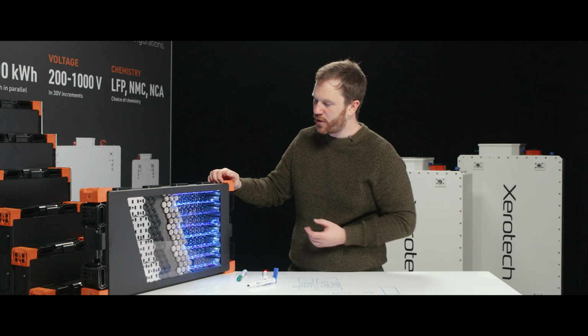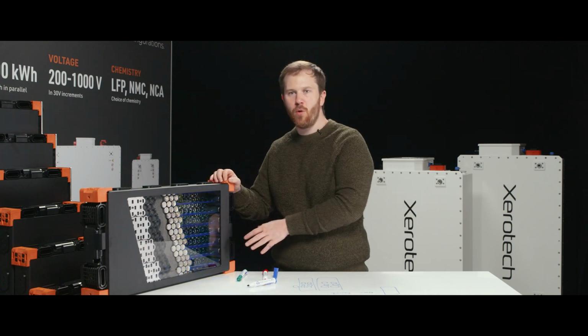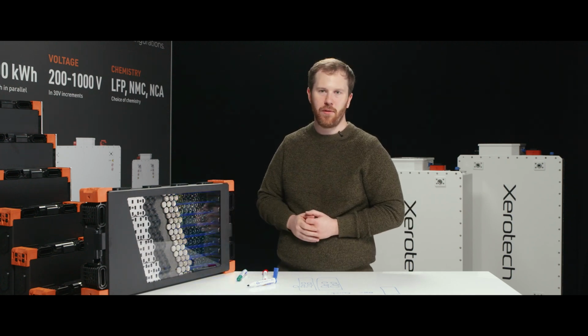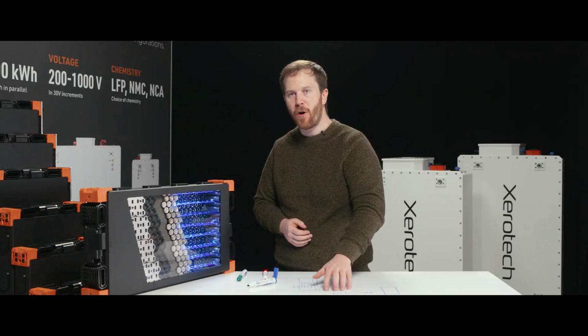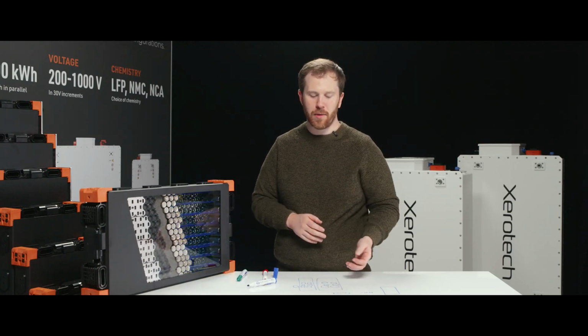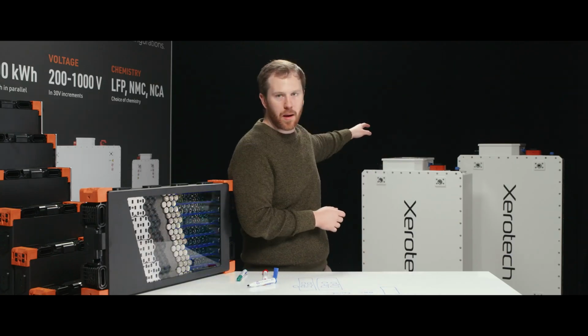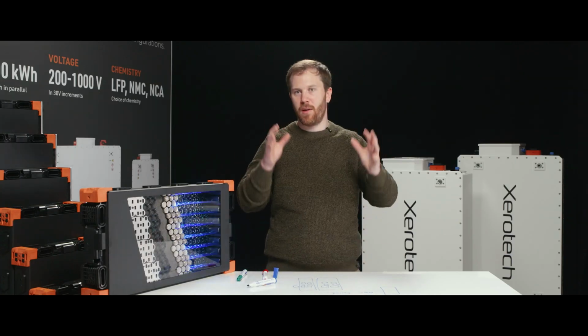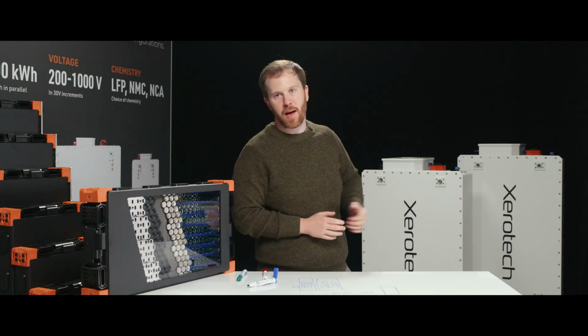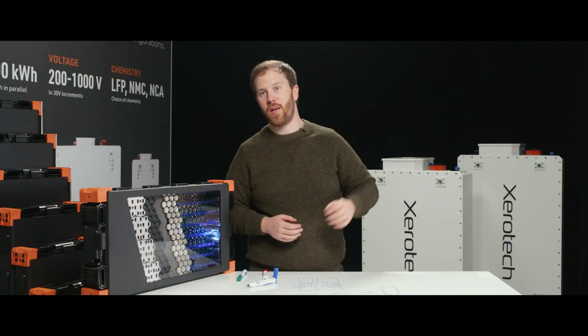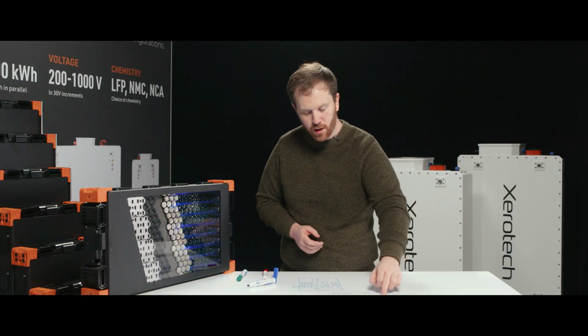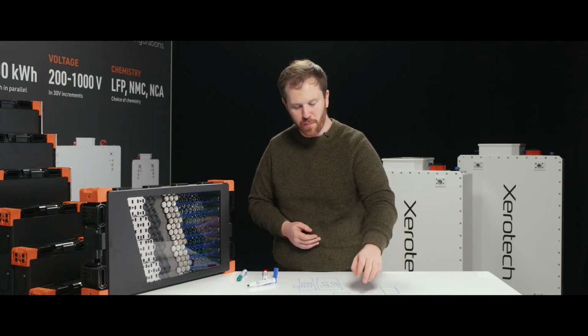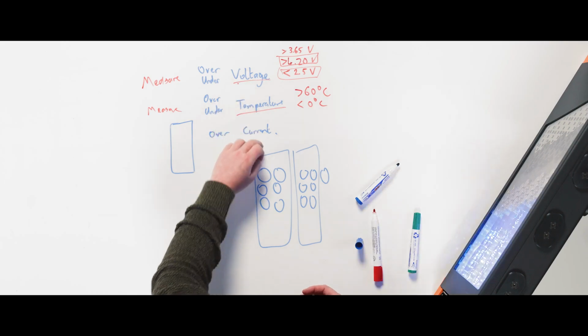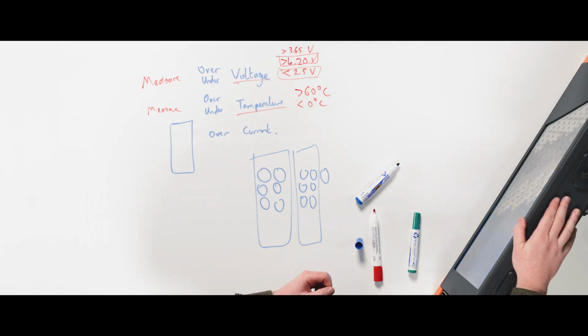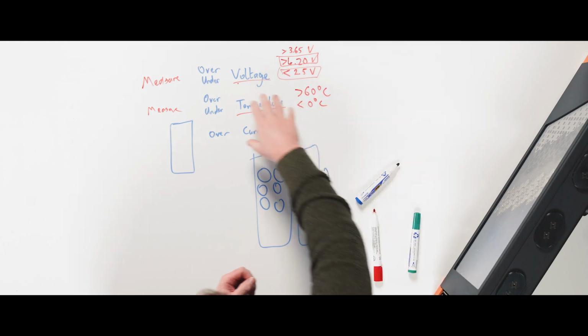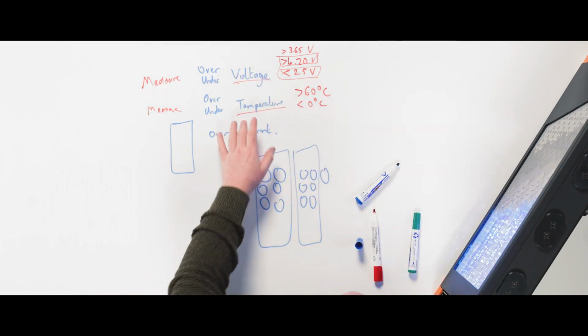The final piece in relation to current is virtually no manufacturers will measure current at a module level. It doesn't make a lot of sense. You could infer this through voltage drop, but that's usually done at your main battery management system, your system level, what we call our BDU, or battery disconnect unit, through a current sensor, a current shunt. So you've got to look at these from a safety perspective. It's very important. These are the main things you can control. And what's interesting to point out, for a module, it actually has no control over any of these things. All it can do is measure it.